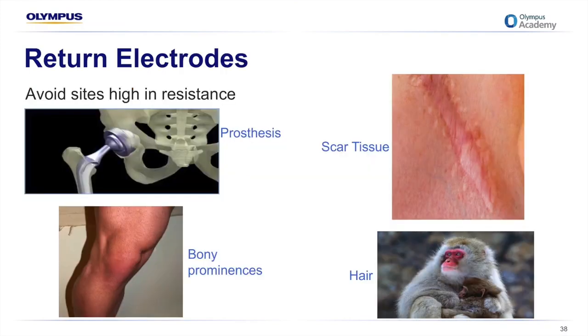Monopolar return electrodes have many safety considerations. Thoroughly assess and document skin integrity before and after the procedure. Always select a new and unopened disposable adhesive dispersive pad appropriate for the patient's size and weight. Never use a pad that has been left open, and never cut a pad to custom fit a patient. Pad placement is key to avoiding burns.